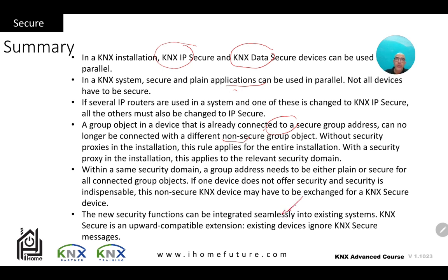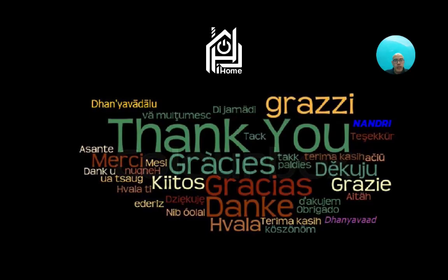A non-secure device will not read the secure data, and it will be ignored. Even the secure devices you have, you can implement them in a secure way or in an unsecure way. If you choose to cancel the security, then they work like normal devices. If you did not apply an ETS password on the ETS file, security will also be disabled. So if you are applying security, then the ETS password on the ETS file is mandatory, and this is done to protect the keys inside the ETS file itself, and all of this should be kept in a secure place. That was KNX Secure.